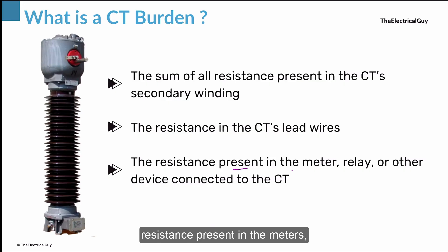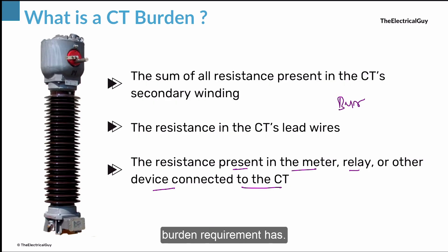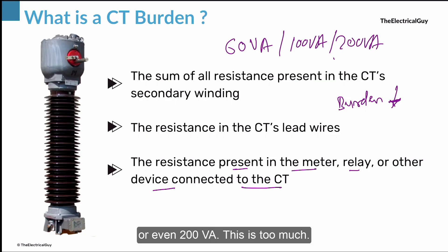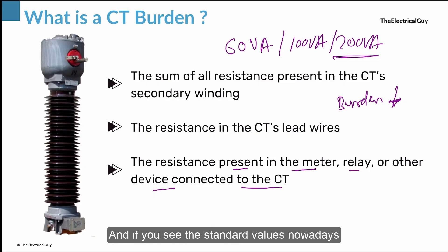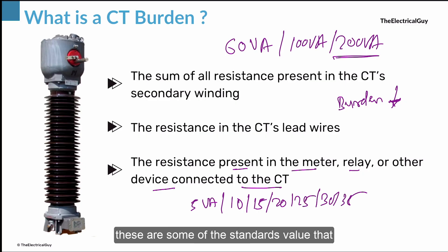The third important parameter is the resistance present in the meters, relays, or other devices connected to the CT. Since we are now in the digital era, all meters and relays have gone digital and the burden requirement has significantly dropped compared to 20–30 years ago when everything was manual and requirements were very high — we have seen CTs rated at 60 VA, 100 VA, or even 200 VA. In today's digital era the burden requirement has significantly reduced. Standard values you will see on the nameplate nowadays are 5, 10, 15, 20, 25, 30, and 35 VA.